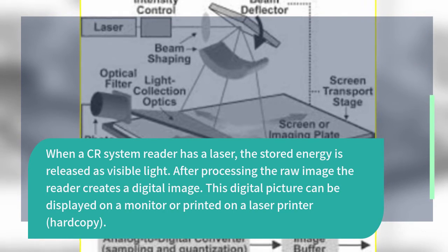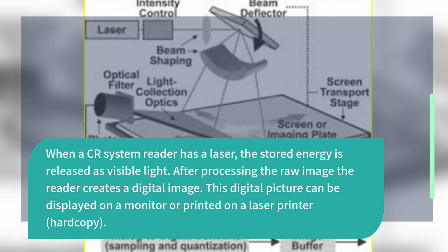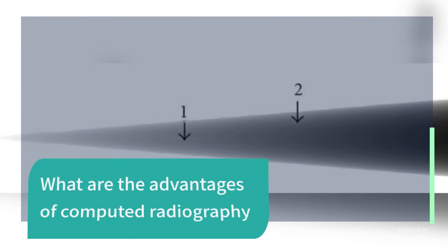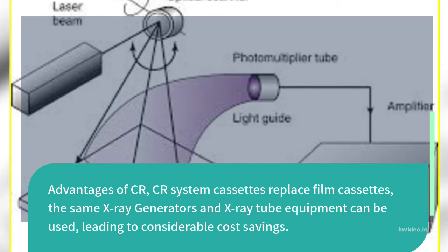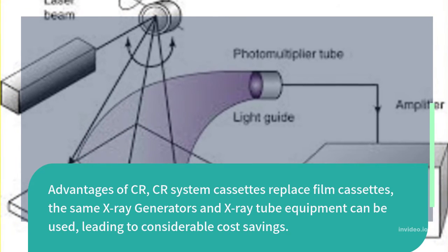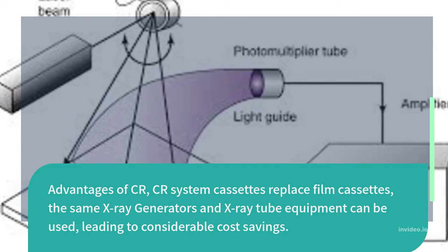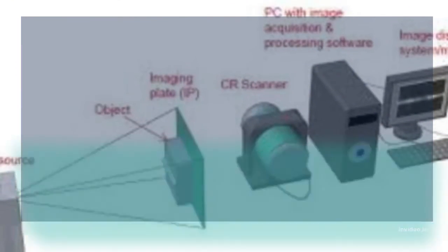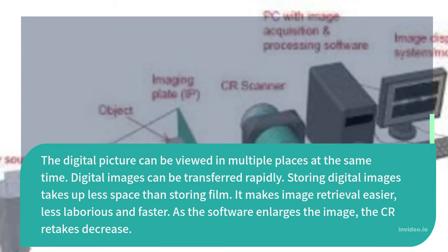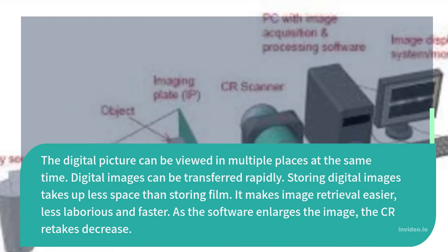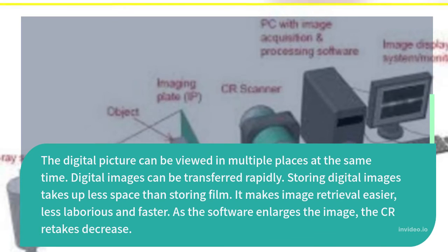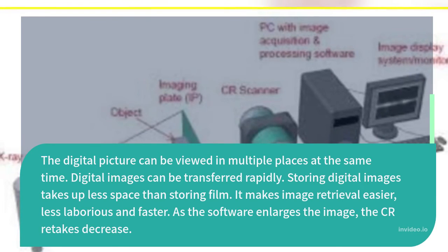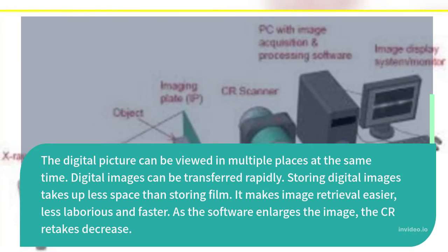What are the advantages of computed radiography? CR system cassettes replace film cassettes, and the same X-ray generators and X-ray tube equipment can be used, leading to considerable cost savings. The digital picture can be viewed in multiple places at the same time, and digital images can be transferred rapidly. Storing digital images takes up less space than storing film, making image retrieval easier, less laborious, and faster. As the software enlarges the image, CR retakes decrease.